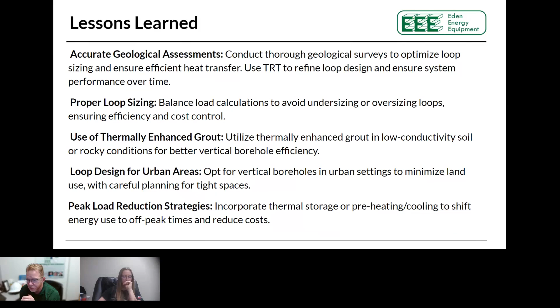Obviously, look into monitoring controls. The control I showed you earlier, I love it. If I ever have to troubleshoot a unit, I don't need a tech on site, I can tell you what's wrong with that unit. I've got 100 data points every 10 seconds for 18 months.